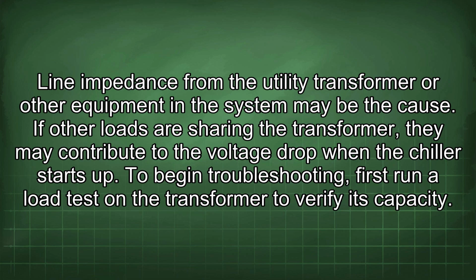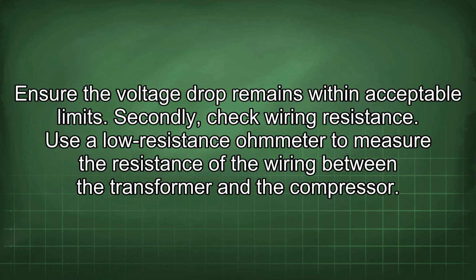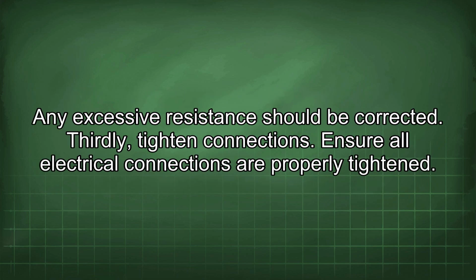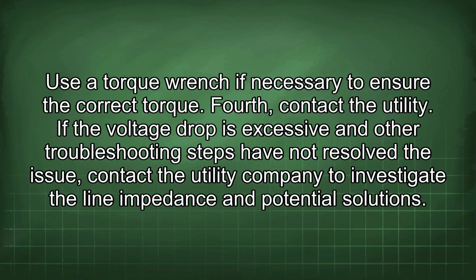To begin troubleshooting, first run a load test on the transformer to verify its capacity. Ensure the voltage drop remains within acceptable limits. Secondly, check wiring resistance. Use a low resistance ohmmeter to measure the resistance of the wiring between the transformer and the compressor. Any excessive resistance should be corrected. Thirdly, tighten connections. Ensure all electrical connections are properly tightened. Use a torque wrench if necessary to ensure the correct torque.